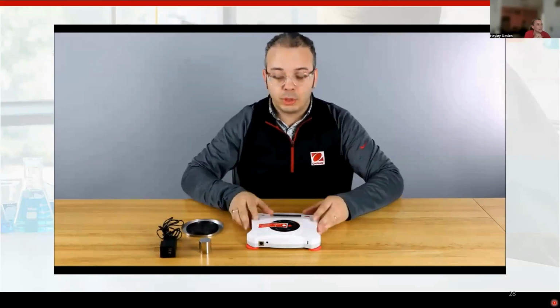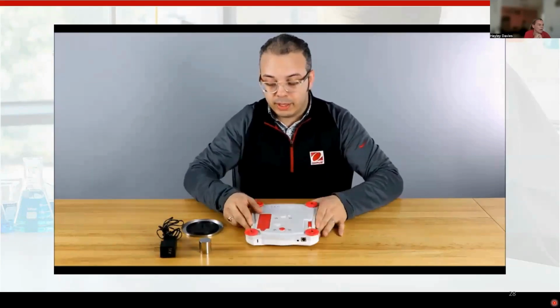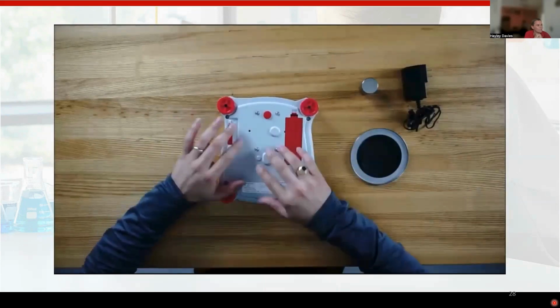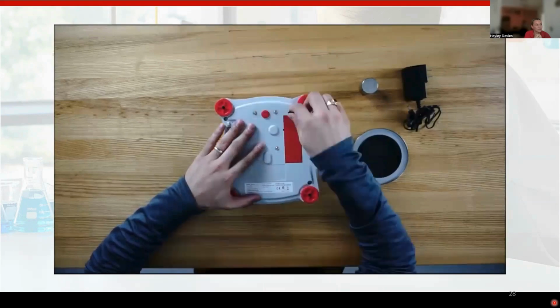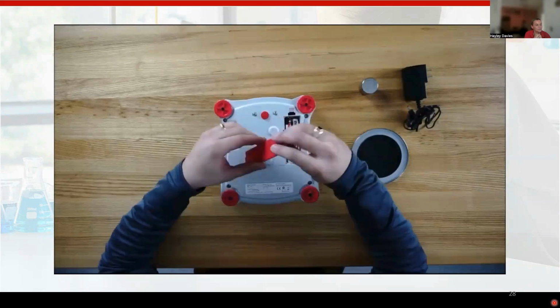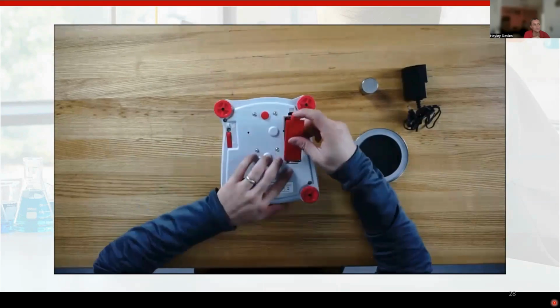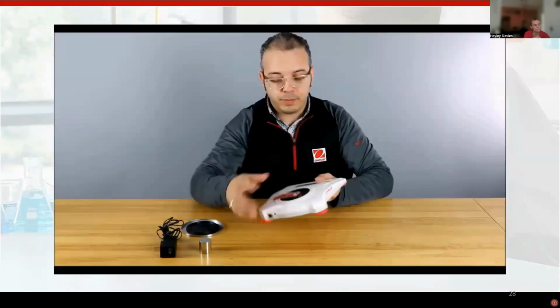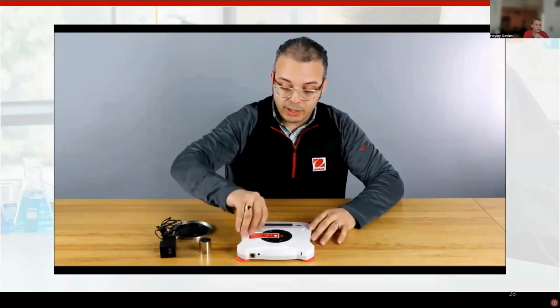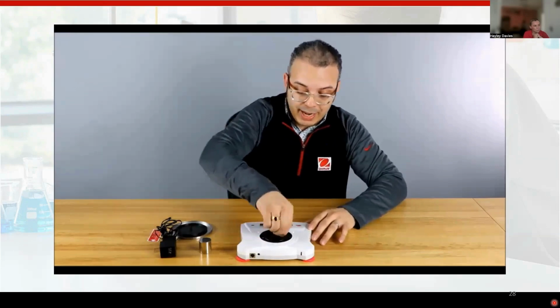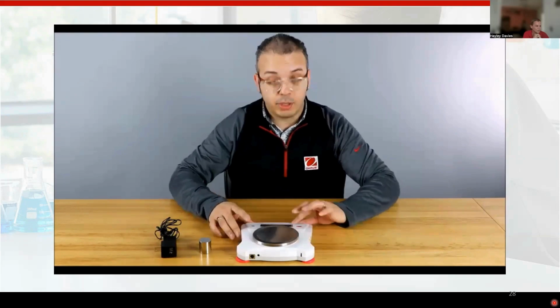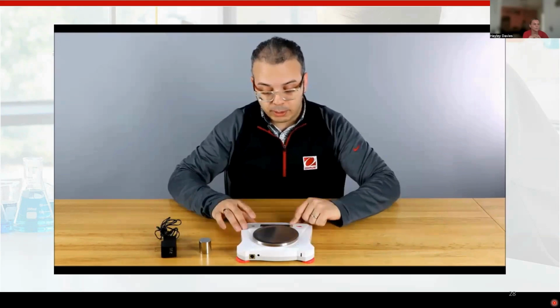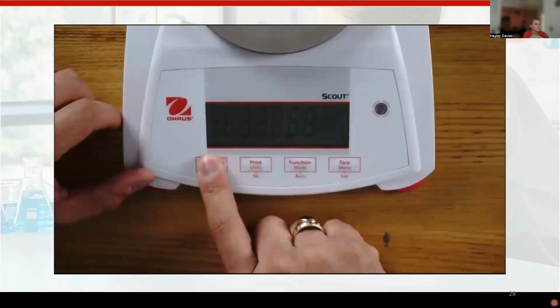We can explain. So we've just taken the box out, and you've got the weighing pan, the power supply, and the calibration weight. You've got an LFT lock, so if it's an approved balance, this is where your weighing hook will be. If you do have a Scout and you're not sure if you've got a weighing hook, that's where it will be. There's a little button where you take the red cap off underneath, and you can just screw that in. When you take it fresh out of the box, there is always a label telling you where the transportation lock is, and you'll see he's just taken the transportation lock off, which protects the balance. And then the weighing pan is placed on, before you switch the balance on. It's being powered up.